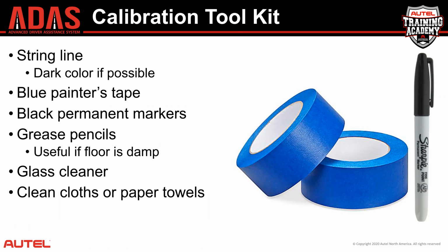So I will generally put a piece of tape down at each location I have to mark a spot using my plumb bob or a laser, and then mark the spot on the ground. And generally you'll have a good 6, 8, 10, 12 pieces of tape on the ground marking different spots for performing calibrations. So you'll go through tape pretty quickly, especially if you're doing calibrations on a regular basis. Oh, I should have pointed out in the beginning of consumables, the reason I'm even bringing up consumables is because you're going to have to keep buying these over and over again. You may want to think about that shop supplier consumables fee in your calibration costs.